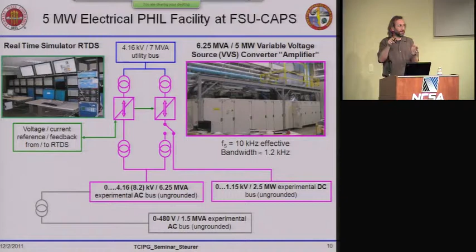Currently, we are facing roughly 300 microsecond delays when we send a signal until it actually shows up at the output. So that bandwidth has to be taken with a grain of salt, because it is a steady-state frequency characteristic, not necessarily transient. It doesn't account for the delay time incurred from sending a change in voltage to when you get it at the output.